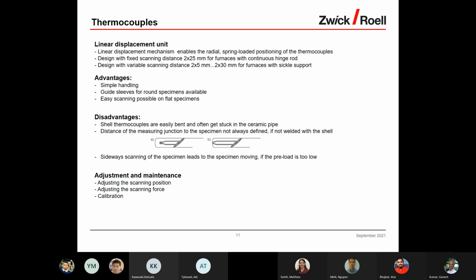The disadvantages: sheathed thermocouples are easily bent and often get stuck in the ceramic pipe. Distance of the measuring junction to the specimen is not defined if not welded with the sheath. Sideways scanning of the specimen leads to the specimen moving if the preload is too low. And the adjustment and maintenance: adjusting the scanning position, adjusting the scanning force, and calibration.